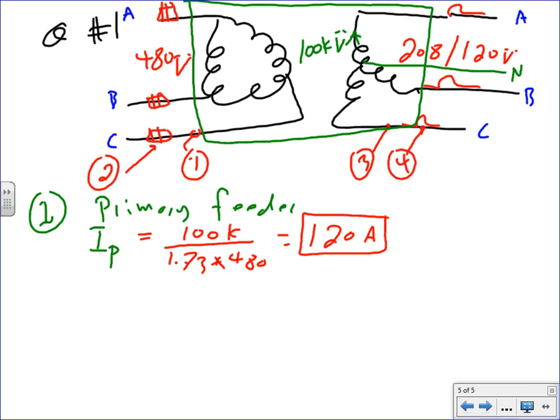Here's how I do it. We start with the load. We size the load, and if it's continuous, we multiply by 1.25. Then we size the transformer. Now the transformer accommodates the 1.25. Then we size the conductor, so we don't have to multiply by 1.25. Oh, okay, that's how they do it in the D-wall. Yes, I know that, and my coach is doing the same thing. I'm going to do it this way.